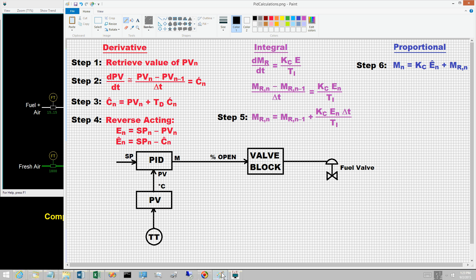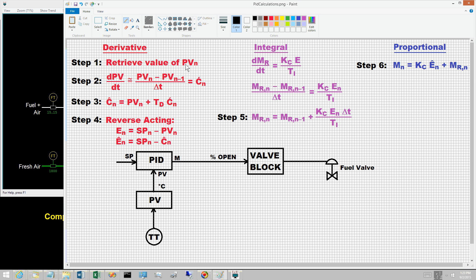The present objective is to present a computational procedure for the basic PID control equations. Obtaining a practical computational procedure requires that additional issues be addressed; these will be mentioned but details will be deferred to subsequent videos. Step one involves retrieving the current value of the input configured for the PV, obtaining PV sub n. The value of the PV from the previous execution is PV sub n-1.